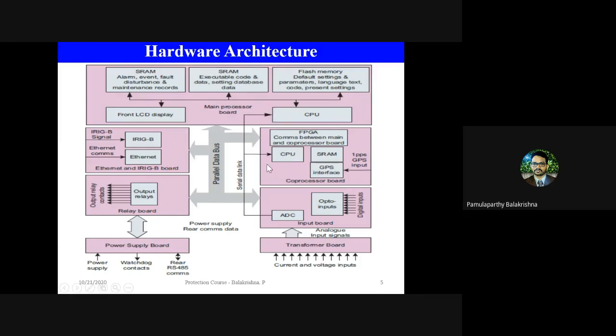Okay. So one of the advantages of a digital relay is that it has two dedicated processors. One is called the main processor, and the other is known as the coprocessor. The main processor is majorly responsible for executing the protection tasks, basically to run various protection functions related to voltages, currents, frequency, all those things. And it has various logics and settings for how it has to execute and function. So everything is embedded as logic inside the main processor board.